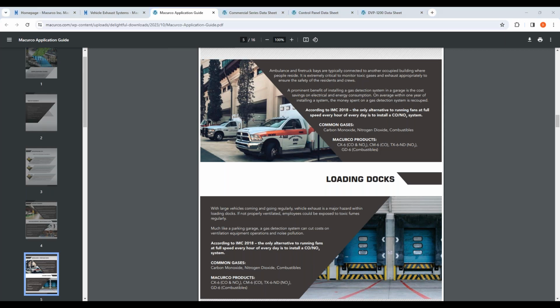Well, the only thing I would add is there's one state that is the oddball to this, that has changed the code in that they will not allow the combination sensors on the wall, and that's Florida. In Florida, you would have to put the carbon monoxide sensor down at breathing level and the nitrogen dioxide up within 18 inches of the ceiling, because of their interpretation of what happens when nitrogen dioxide is introduced into the atmosphere. So just know that Florida is a little bit odd in that they're the only state in the country that will not allow our CX6 combo sensor.